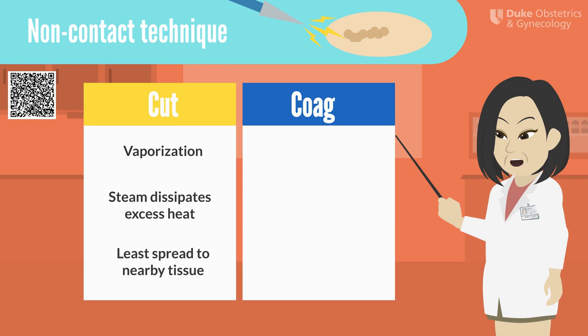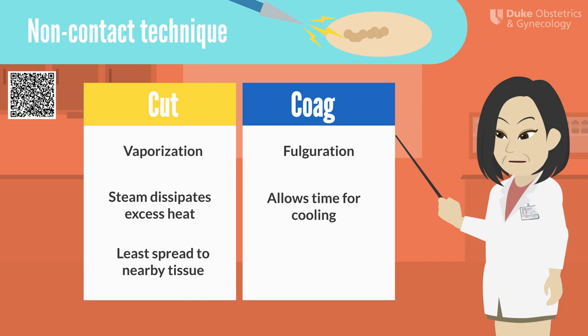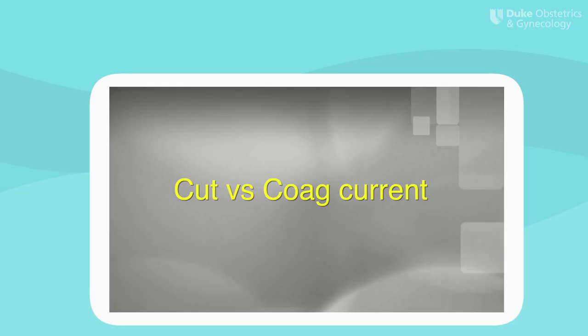What if we were to continue to use the non-contact method but activate the blue coag button? This would result in fulguration, which is the charring and carbonization of superficial tissue. The interrupted nature of the coag waveform is key here. Given that the current is only on for 6% of the time, the tissue is given time to cool between activations. This forms a coagulum on the tissue surface. Using coag without tissue contact causes a superficial char on the tissue, which may be good for superficial oozing, but is not as helpful if you are looking to penetrate the tissue deeper.